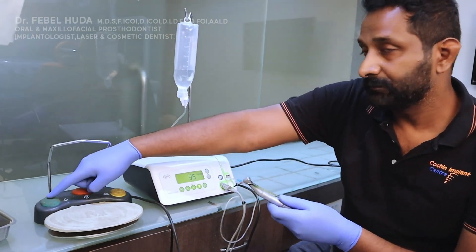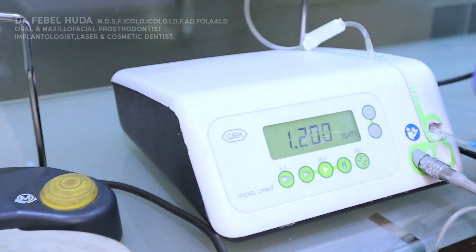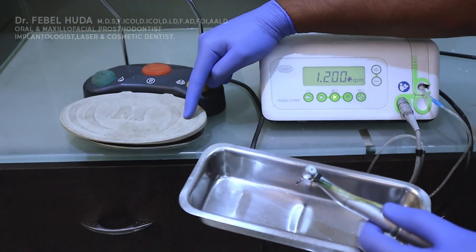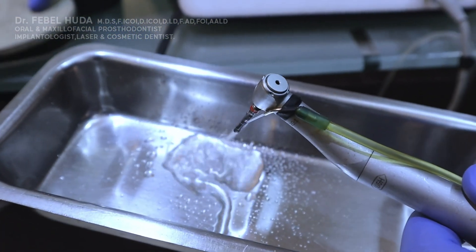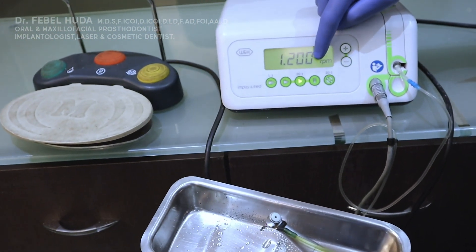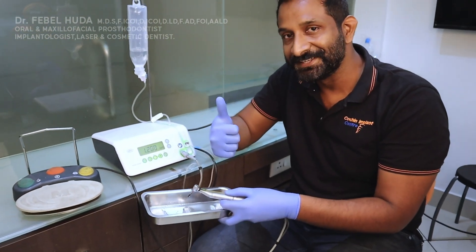Finally, let's see how the saline works. Pressing the green button activates it — switching to drive mode, you can see the saline is on. When I press the foot switch, the pump starts working and saline flows. Switching saline off removes the saline indicator, and pressing the pedal then gives no saline output. This is another function you can control with your foot. Looking forward to the next video — bye!